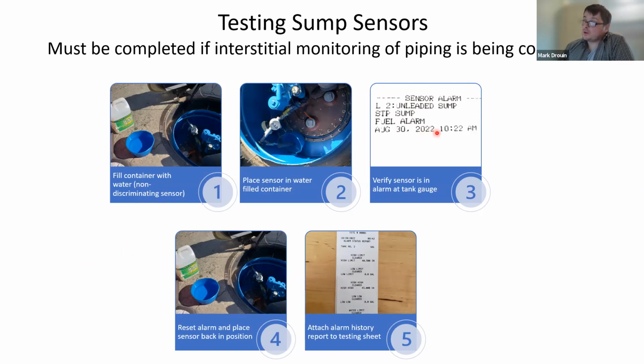So you place the sensor in there, it should go into alarm. You want to double check everything, make sure that this is the right sensor. This is the unleaded sump sensor, and it went into alarm, so your sensor was tested. You clean off your sensor, place it back into the position it needs to be, and then you print off your alarm history report.